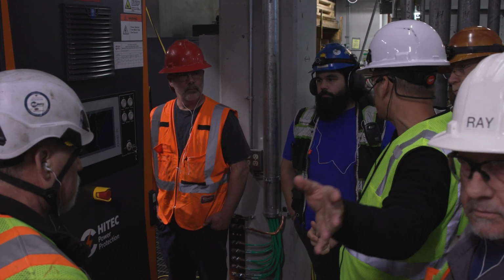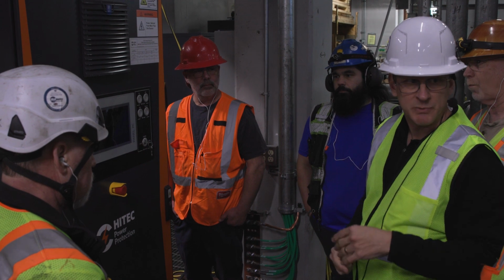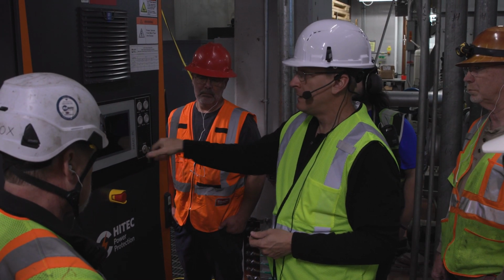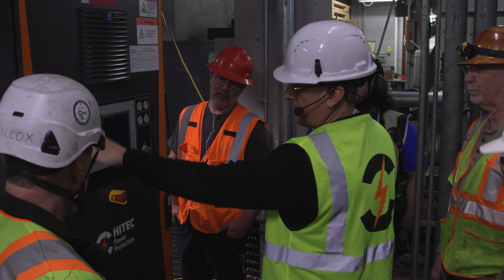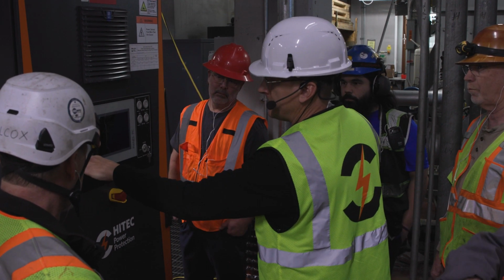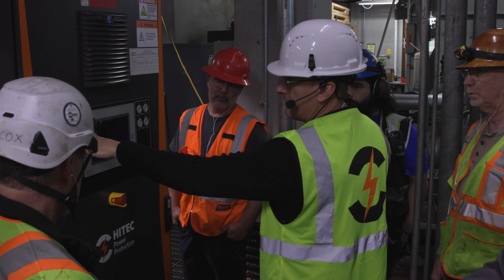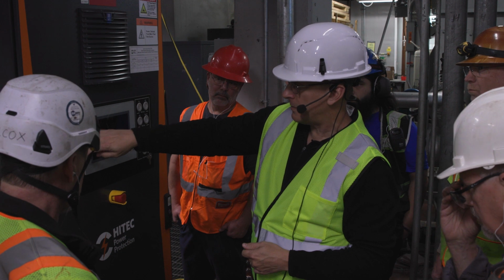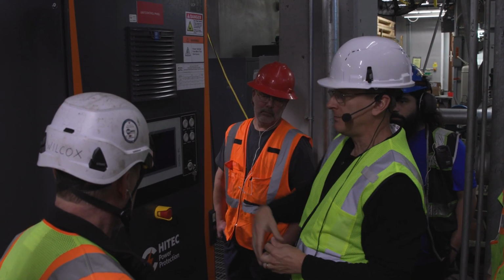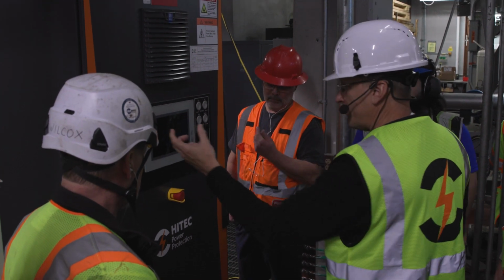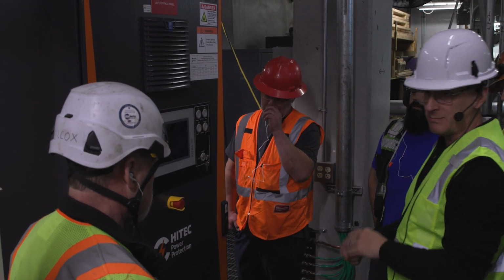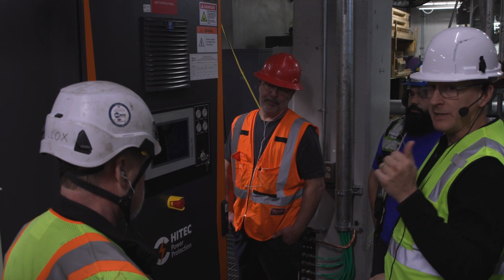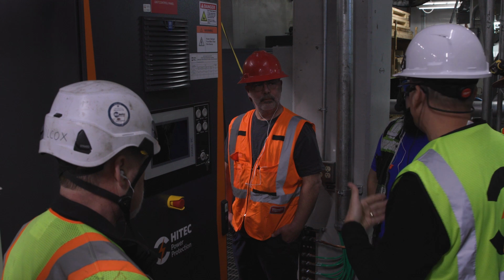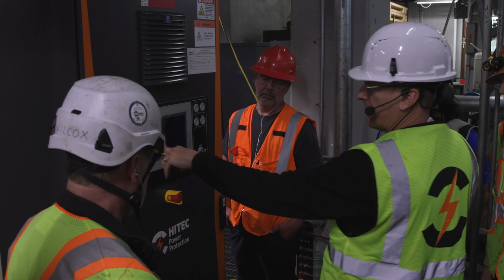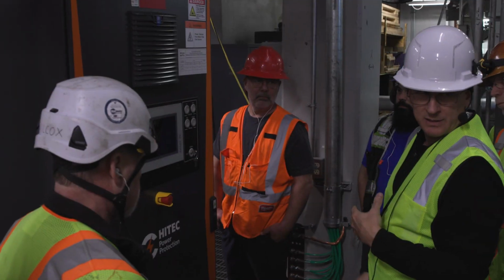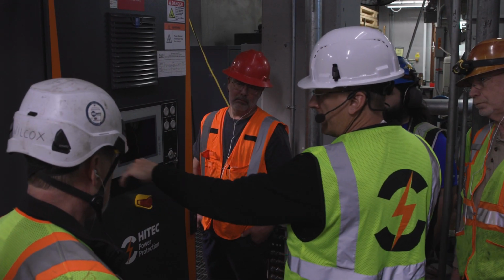Then you can connect to the SCADA box and control it at the SCADA box, which I'll show to you as well. On your left-hand side, you've got some other lighting indications. These are only lights, they're not buttons. They're just giving you an indication of failure, warning or attention, or just straight operational. Your failure light is going to be red. Anytime you have a failure condition or a red light, it means the system is shutting itself down. It will go to bypass first when it shuts itself down, if bypass is available, okay? And then you've got a light that indicates whether you have an active warning, a lower level warning, and a light indicating whether it's operational or not.